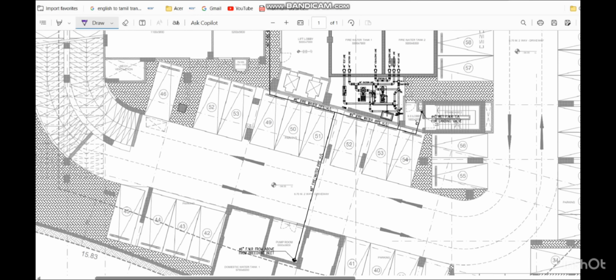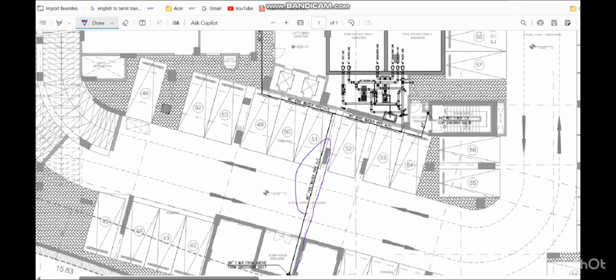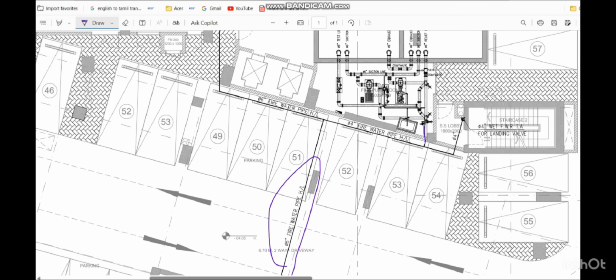And coming to the second mistake, you can see here for the fire pump room. At this point the breeching inlet line comes, which is a 6-inch line, and coming to the fire pump room, you can see this discharge line which is going this way. So this is the 6-inch pipe going to serve all the floor levels, which is a combined riser, and this is the individual riser which is the 4-inch pipe.